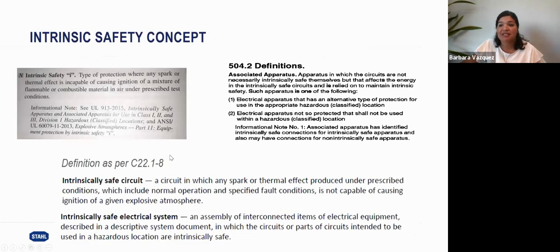Okay, but let's go back to the standard and intrinsic safety. So what is intrinsic safety? The NEC defines it as a type of protection where any spark or thermal effect is incapable of causing ignition of a mixture of flammable or combustible material in the air. An intrinsically safe device will use an associated apparatus. Actually, associated apparatus is the correct name of a barrier. We always call it, I need a barrier, I need an IS barrier. Well, it is an associated apparatus.